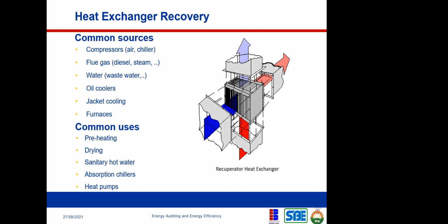Then the next one is waste water. If you have hot water that is being wasted, you can recover that heat from the waste water. Then you have oil cooler. If you look at your diesel generators, right? If you notice, you need to add oil to your generators, and what that oil does is that it circulates around your generator and provides kind of lubrication around the moving parts of your generator. But what you also notice is that oil usually gets hot, okay, and they lose that heat to the environment, right?